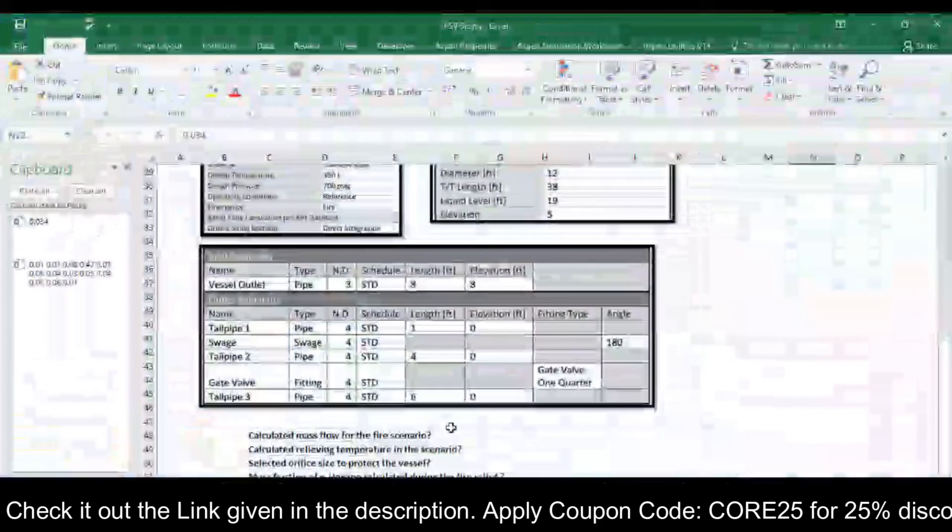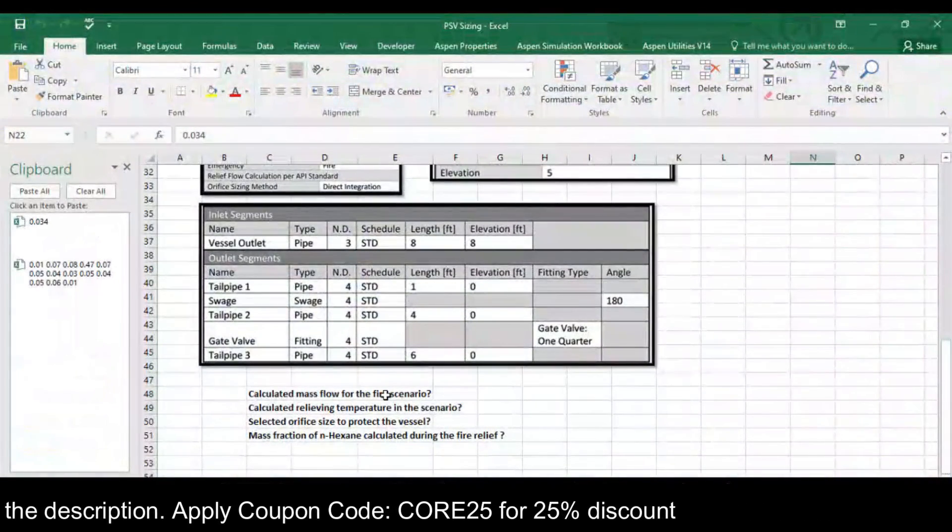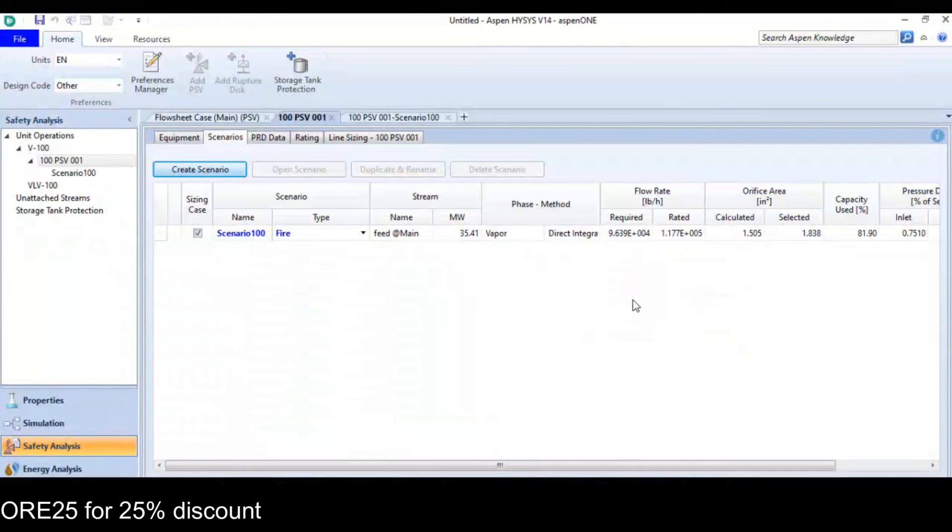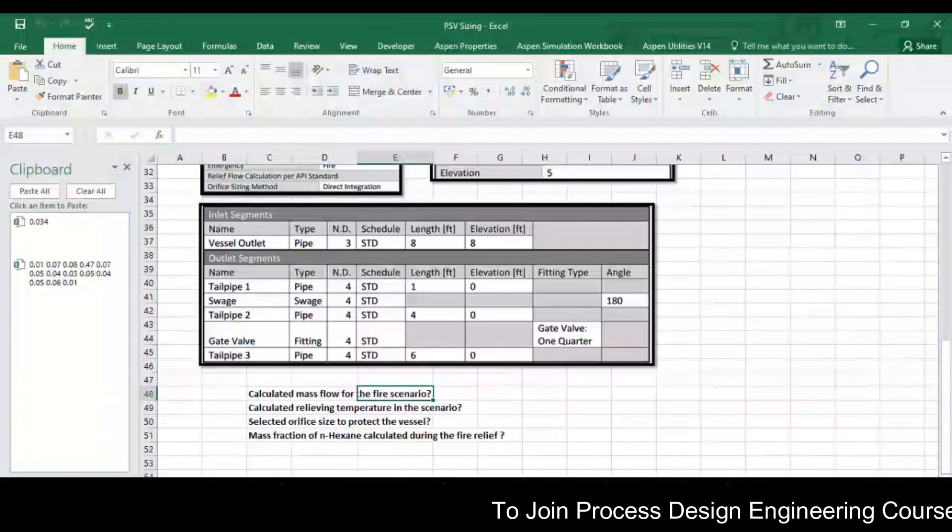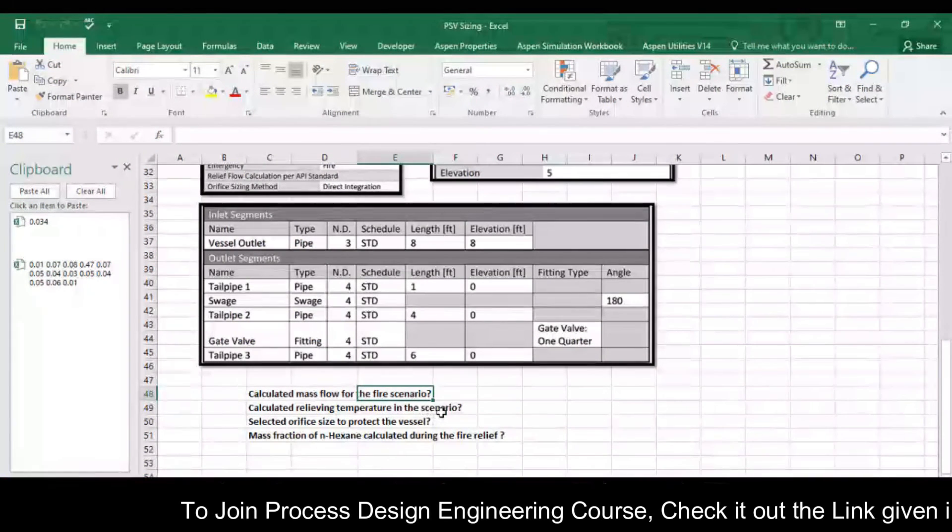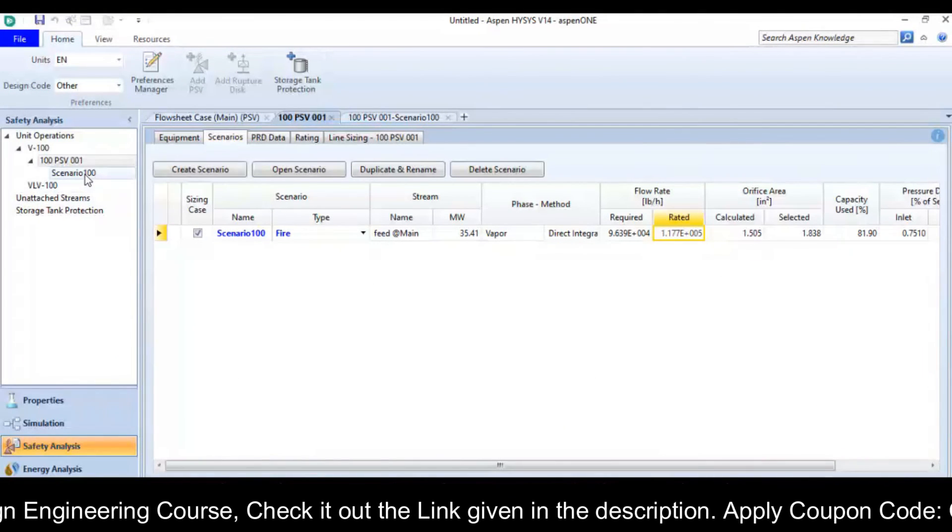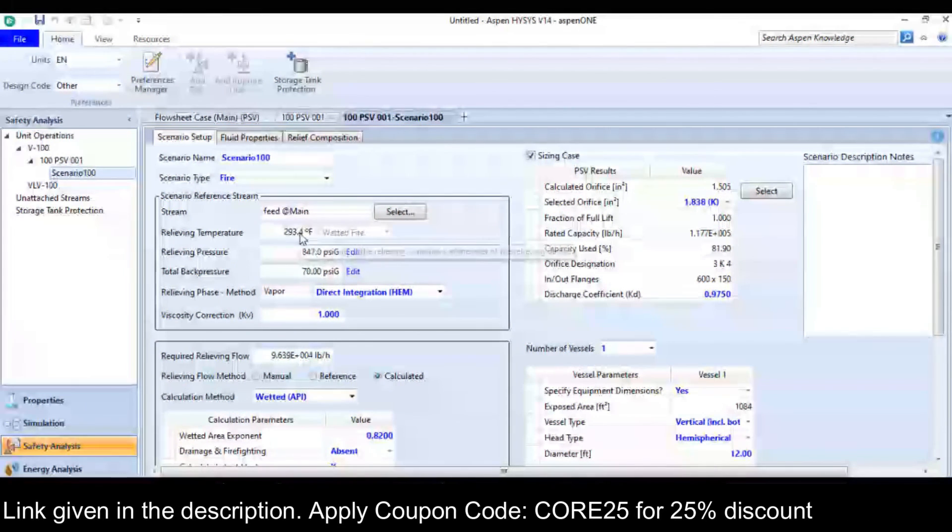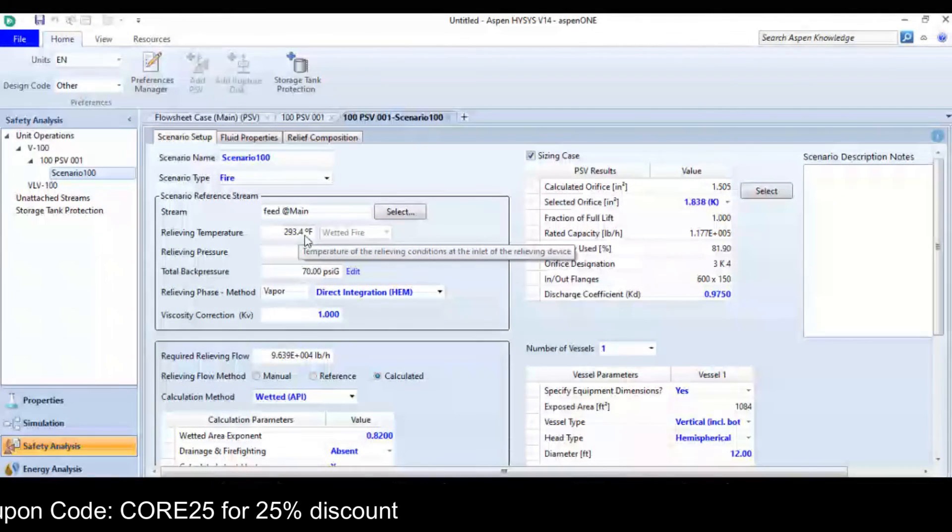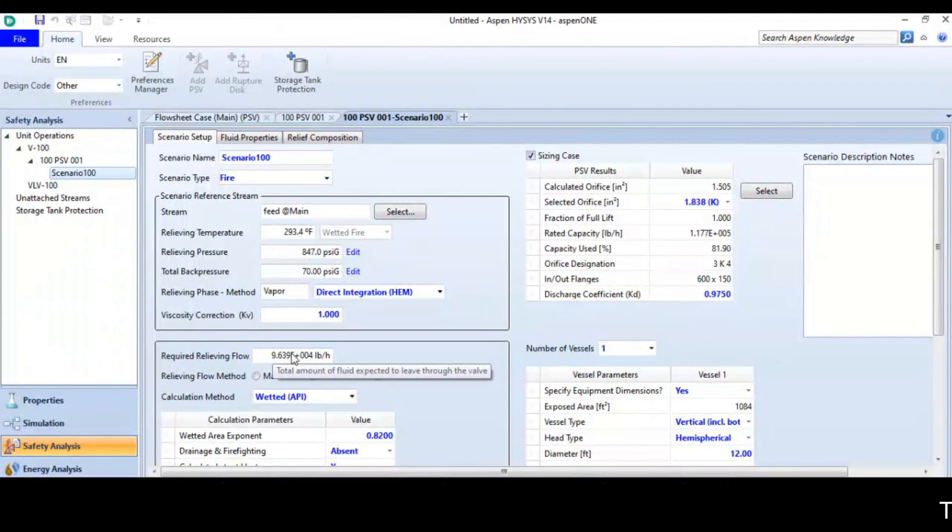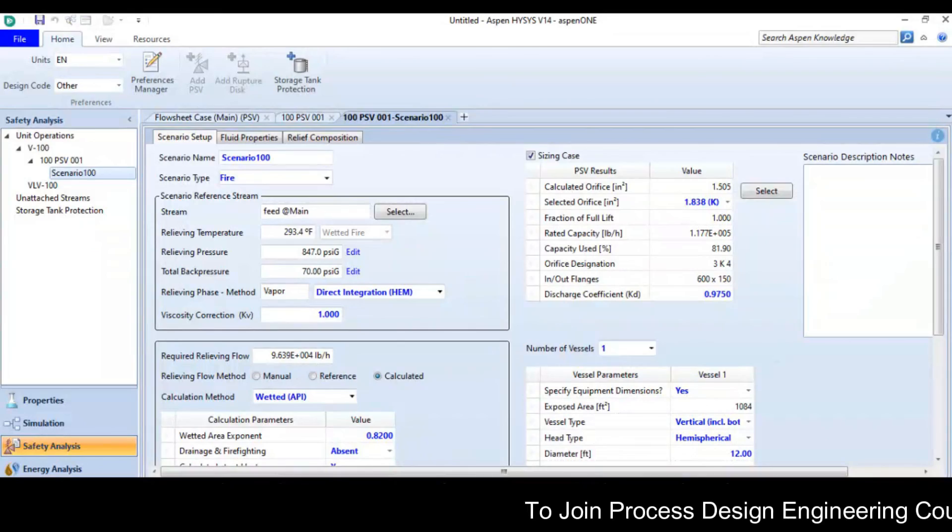Now look at the calculated mass flow rate for the fire scenario. If you want to see the flow rate, you can see there. This is your required and the rated flow rate. The calculated relief temperature in this scenario. So if you go to scenario, you can see that the calculated relieving temperature is 293.4 Fahrenheit. The required relieving flow is 9.639 exponent 4 pounds per hour.